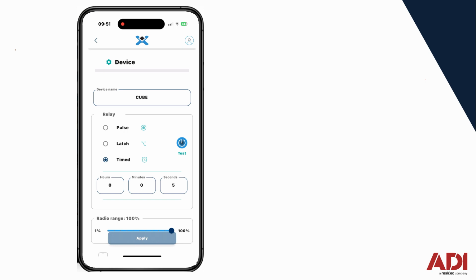Pulse is a simple pulse output, momentary output, somewhere between 3/4 of a second and a second. That's if you're going to connect it to an access control device where you don't want to increase the lock output time. Then you have latch, maybe directly controlling a light. So you can click the relay once, the light stays on, click it again, the light goes off. And then the last option is timed. If you're going to directly control a lock or mag lock or something like that, you'll have the timed output, which, as the name suggests, is momentary, much like pulse, but it gives you a timed output.